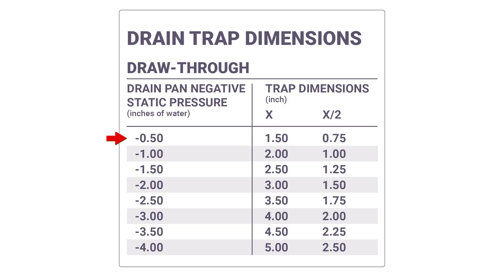At that point, if you're already making it larger than the standard pre-made traps, you might as well go bigger — as big as you realistically can. It doesn't hurt to make it bigger other than holding a little more water, which could make it slightly more likely to back up. But if you're fabricating your drain properly with the outlet lower than the inlet by at least a pipe dimension, a three-inch trap is even better. Generally, if you know the system will always be 0.5 inches or less on the return side, one inch is enough — but designing for up to a one-inch return static gives you a two-inch trap, and that's safe.